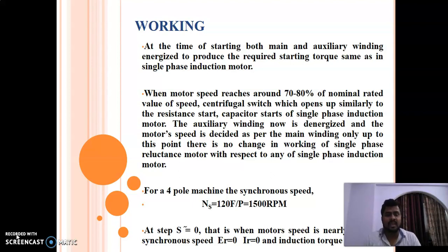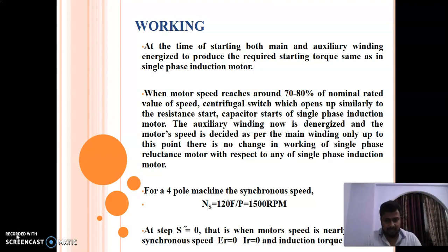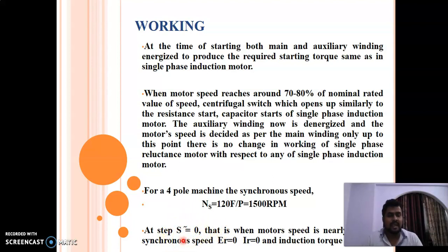The auxiliary winding is now de-energized and motor speed is determined by the main winding only. Up to this point there is no change in the working of a single-phase reluctance motor compared with the induction motor. For a four-pole machine, the synchronous speed will be around 1500 RPM. When the slip is close to zero, the speed is nearly synchronous speed, and at this speed the induced EMF in the rotor will be zero, the current will be zero, and the induction motor torque will be zero.